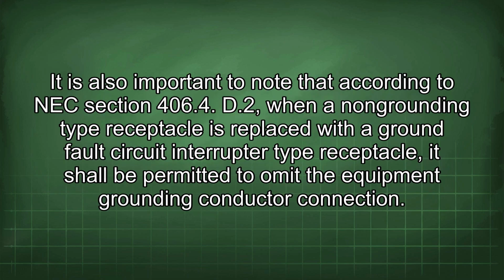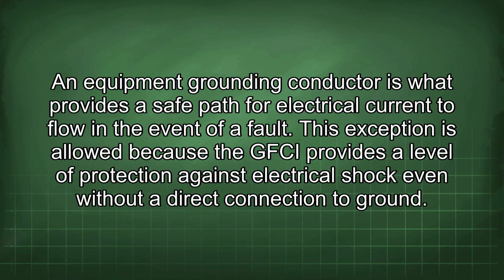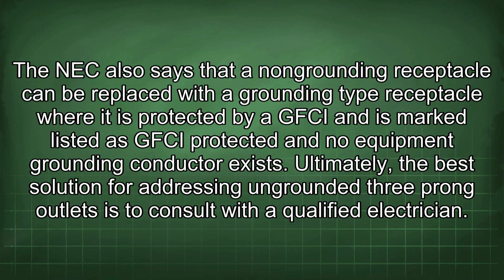It is also important to note that according to NEC section 406.4 D2, when a non-grounding type receptacle is replaced with a ground fault circuit interrupter type receptacle, it shall be permitted to omit the equipment grounding conductor connection. An equipment grounding conductor is what provides a safe path for electrical current to flow in the event of a fault. This exception is allowed because the GFCI provides a level of protection against electrical shock even without a direct connection to ground. The NEC also says that a non-grounding receptacle can be replaced with a grounding type receptacle where it is protected by a GFCI and is marked as GFCI protected and no equipment grounding conductor exists.